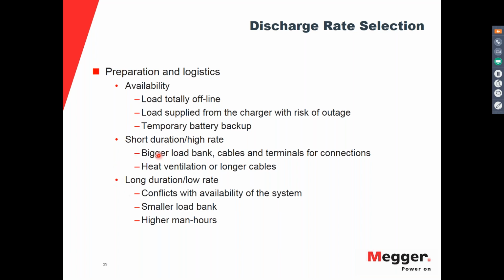For short duration rates, you need a bigger load bank. You need good cables and terminals for the connections, and you need to consider ventilation or installing the load bank outside the battery room. Long duration, low rate tests will conflict with the availability of the system, or you need to bring a backup, and of course you need more man hours to perform the test. So there's a trade-off when you select the rate, but especially you can't select just any value. You need to select according to the duty cycle of the battery.